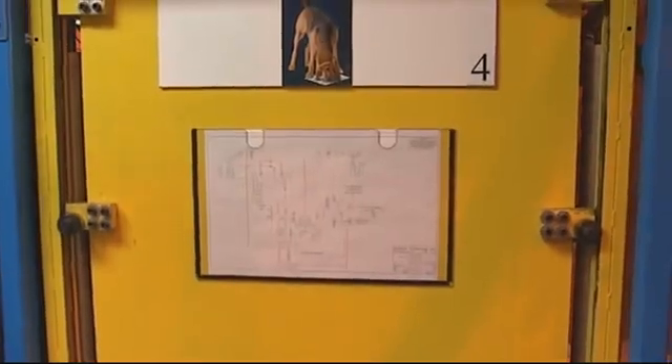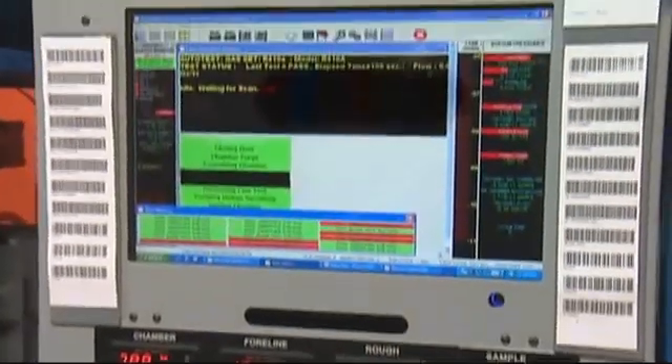Mark, I know you can tell what this is. The hound dog! So tell me exactly what this test does. We're checking every point at one time for a potential leak. And if it has a leak rate higher than half an ounce a year — 0.5 ounce per year — then it retests. Half an ounce? Wow, that is very, very impressive. That is very, very small.